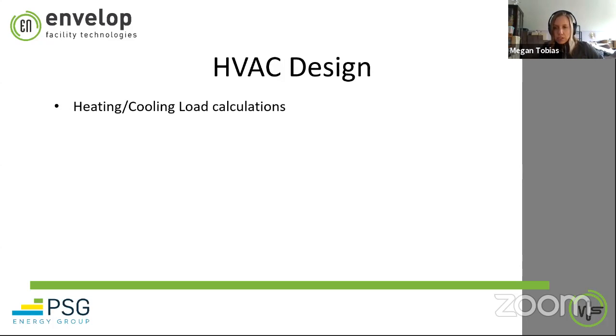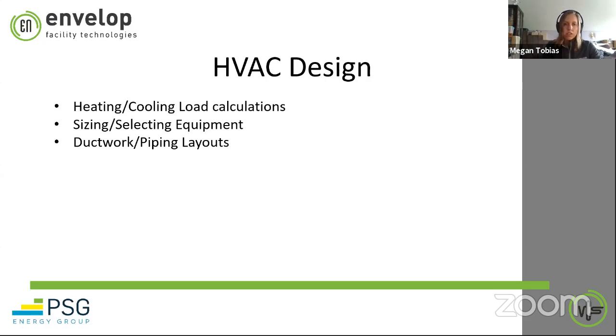So they do all these calculations to figure out exactly what they'll need in order to size and select the different equipment for the space. From there, they do ductwork and piping layouts and draw up mechanical schematics showing where all of that needs to be installed in a building. Then they write what we call sequences of operation—how these various pieces of equipment need to be programmed to achieve the end goal, which is occupant comfort. For example, at the room level, how do we keep it at 72 degrees, let's say?